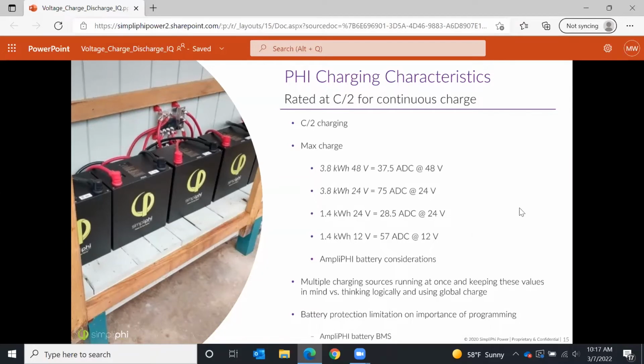So there are multiple ways to combat this. You can use overcurrent protection, or settings like global charge, making sure the whole system is communicating to not charge the batteries too quickly. I like to think of it in terms of system design. I'm a fan of the Sol-Ark inverter, putting everything in one box. That Sol-Ark isn't going to charge the batteries faster than 9 kilowatts, 185 amps DC, no matter if you have the generator running and the PV at the same time. It's all in one box and it all knows what's going on.